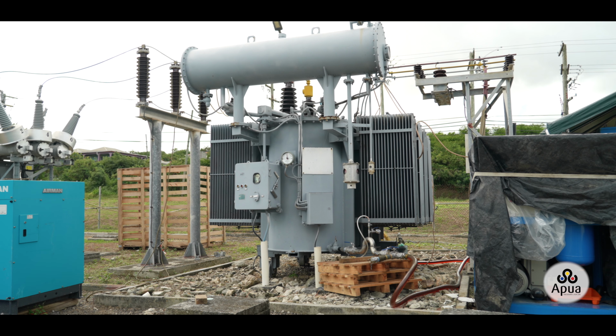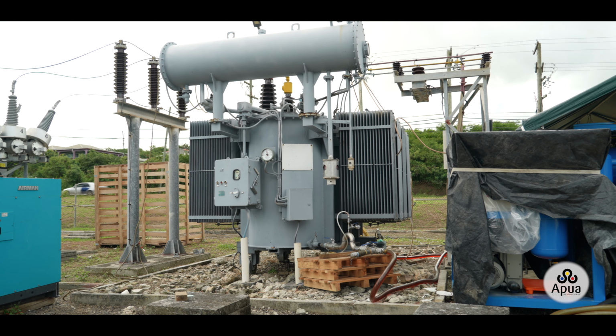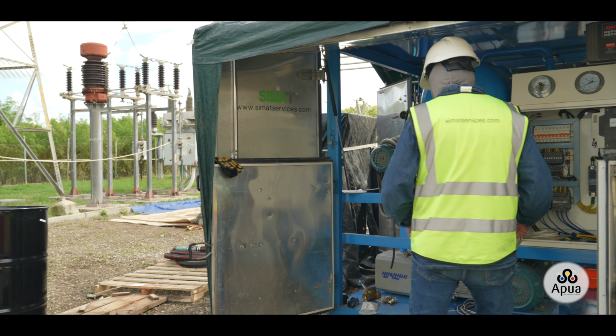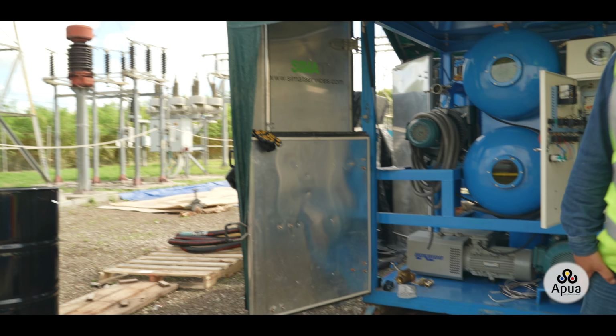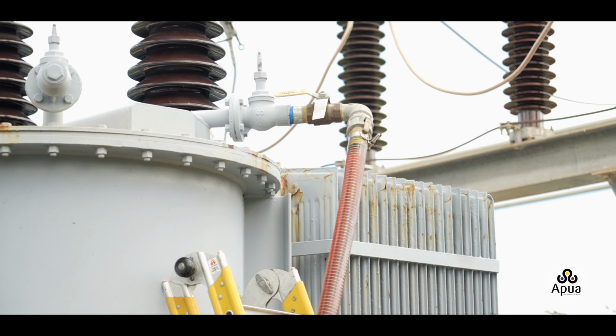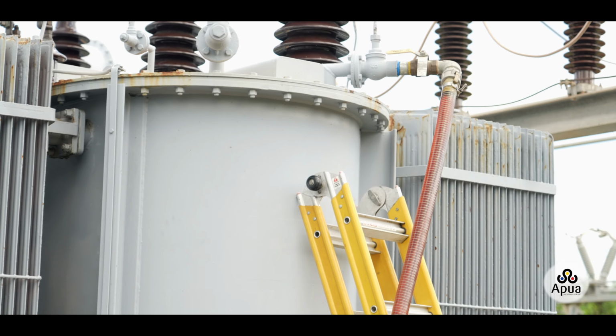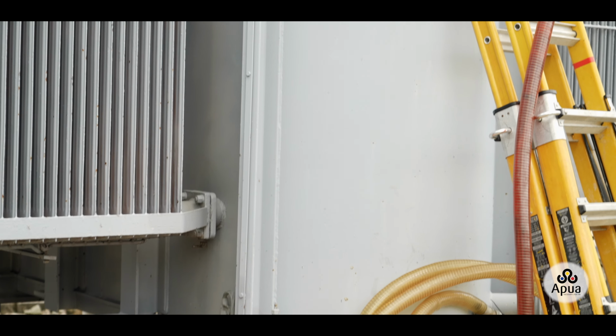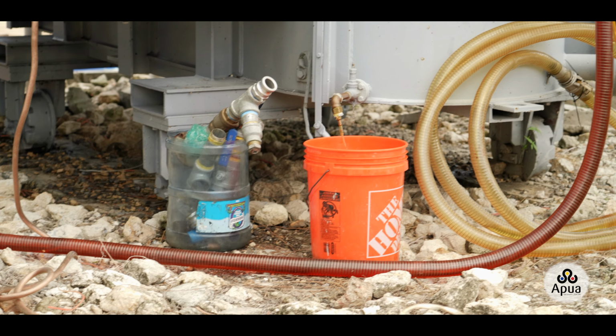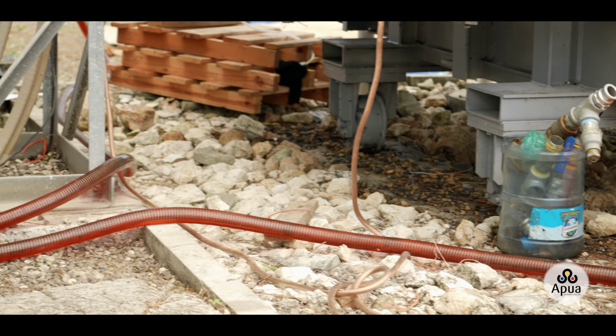The power transformers at the different power substations have been installed for quite some time now. And over time, the insulating oil would have deteriorated. The assessment that was done by a team, SIMAT, out of the States, indicated that some of the transformers, the Belmont transformer, Sweets transformer, Lavington transformer, and one of the transformers at Tango, the oil has deteriorated.